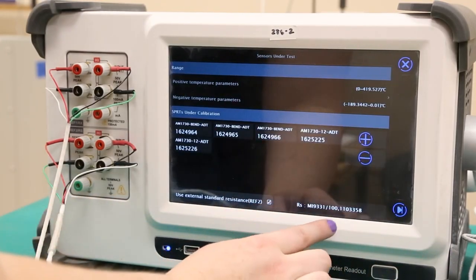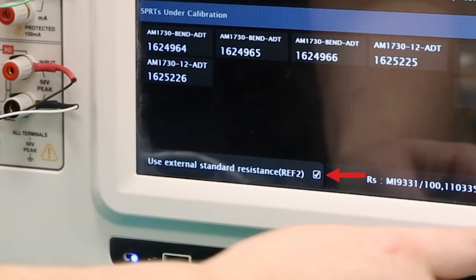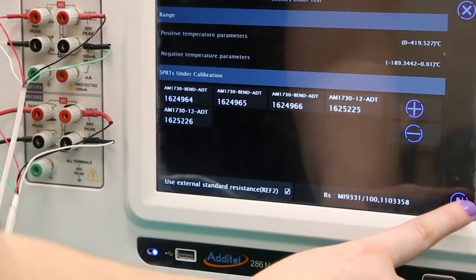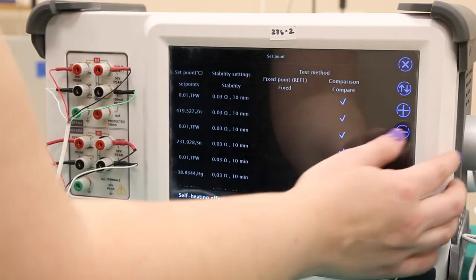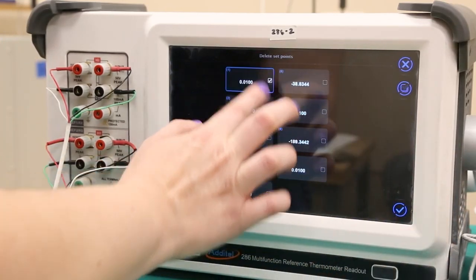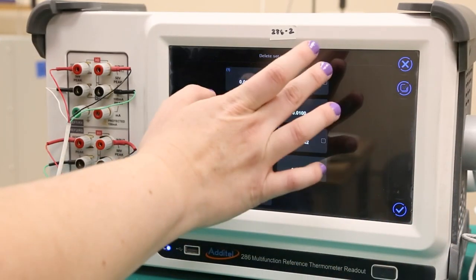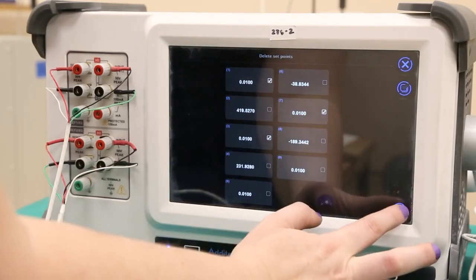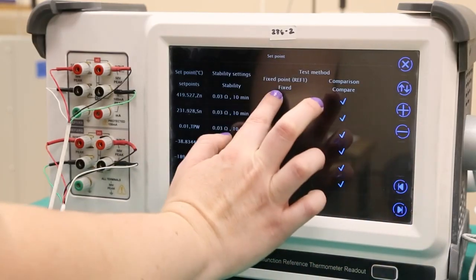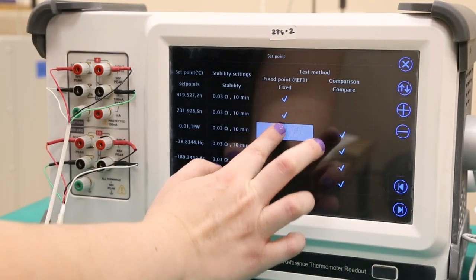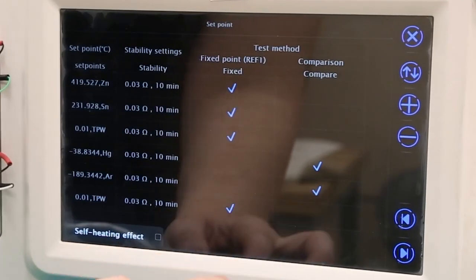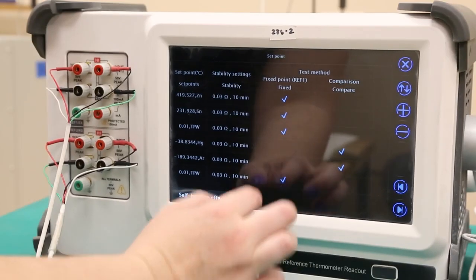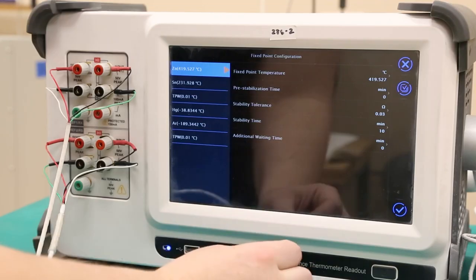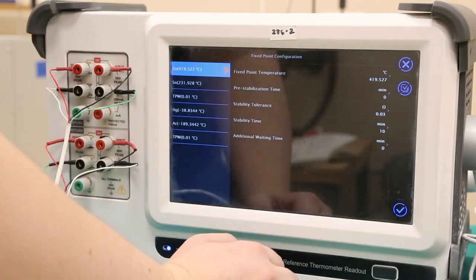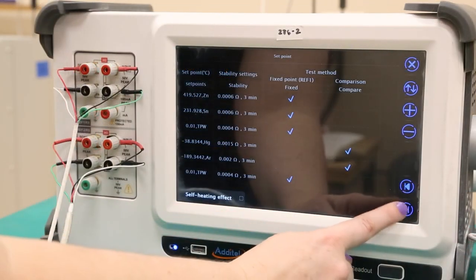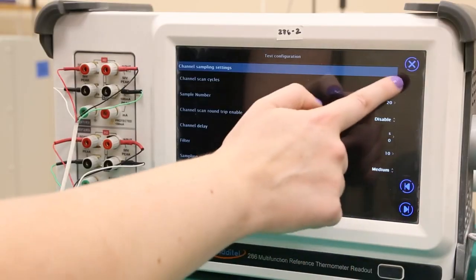Once all probes have been entered, we will check the Use External Standard Resistance option before pressing Next. Here the test method for each calibration point can be changed, and points can be added or removed using the plus or minus keys. We will use fixed point tests for the zinc, tin, and water calibration points, and comparison tests for the other 2. Specific test settings can be changed here as well, by selecting the calibration point you wish to change parameters for. Once each point is configured to your lab standards, press the Next key.